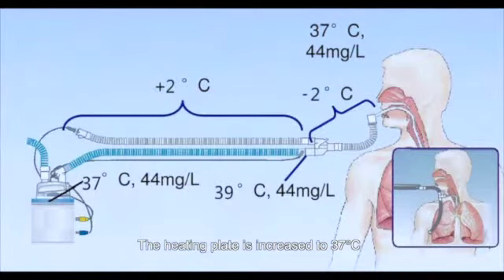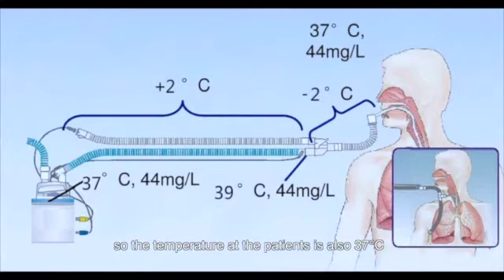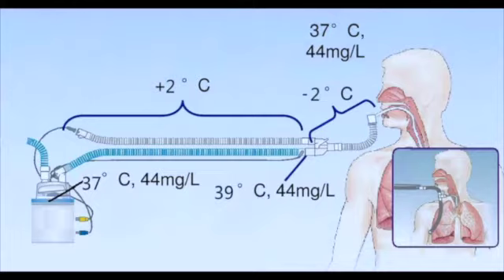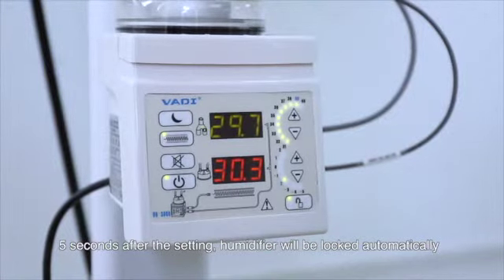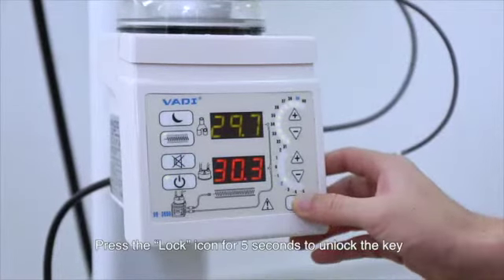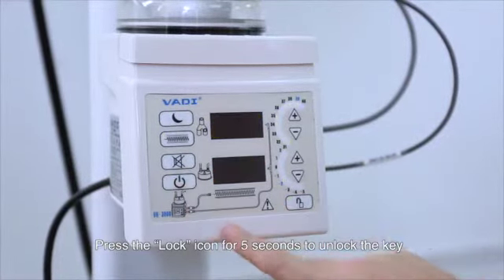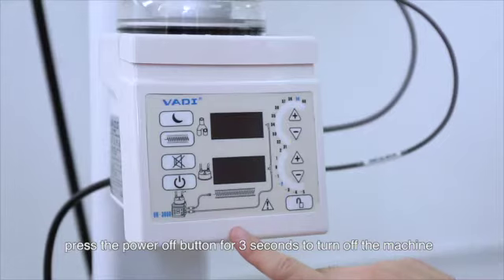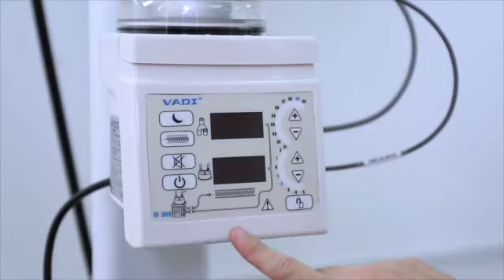The heating plate is increased to 37 degrees. The heating tube is increased 2 degrees. The temperature at the Y end is 39 degrees. So the temperature at the patient's end is also 37 degrees, as 2 degrees have been reduced without the heater wire. 5 seconds after the setting, the humidifier will be locked automatically. Press the lock icon for 5 seconds to unlock the keys. Press the power off button for 3 seconds to turn off the machine.